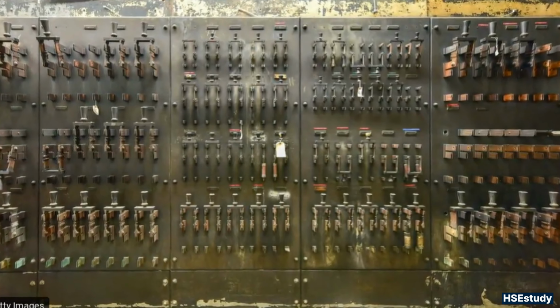NFPA 70E and OSHA mandate a strict live, dead, live testing protocol. You test the meter on a known live source, test the target equipment to verify zero voltage, and test the meter again to ensure it is still functioning. Visual confirmation of an open switch is entirely insufficient.